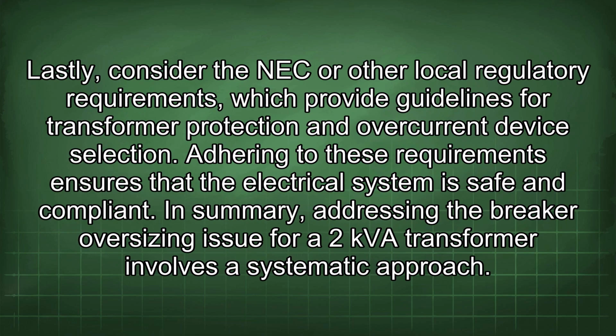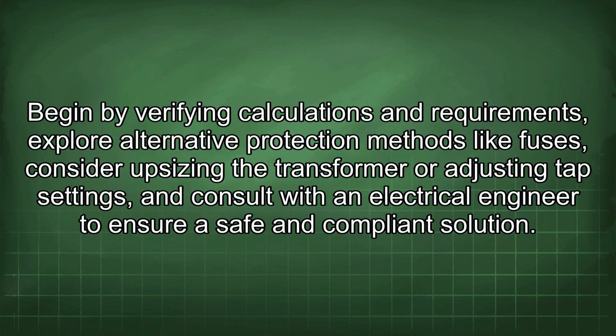Lastly, consider the NEC or other local regulatory requirements, which provide guidelines for transformer protection and overcurrent device selection. Adhering to these requirements ensures that the electrical system is safe and compliant. In summary, addressing the breaker oversizing issue for a 2 kVA transformer involves a systematic approach. Begin by verifying calculations and requirements, explore alternative protection methods like fuses, consider upsizing the transformer or adjusting tap settings, and consult with an electrical engineer to ensure a safe and compliant solution.